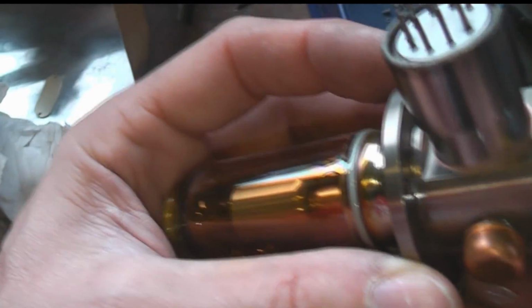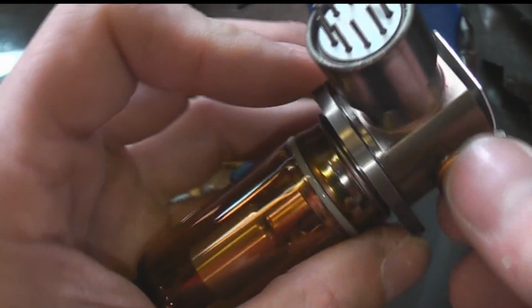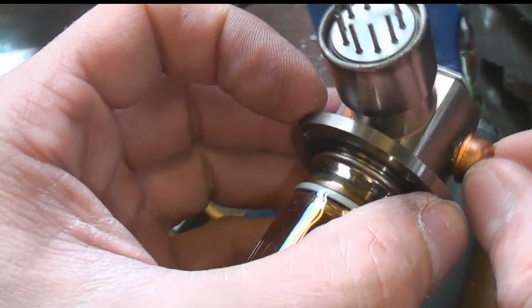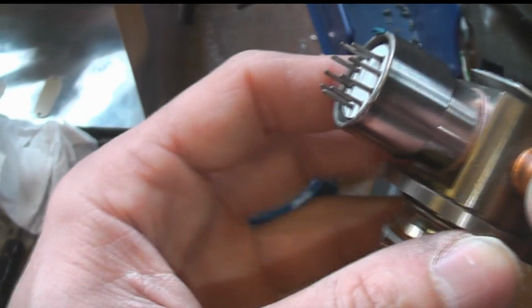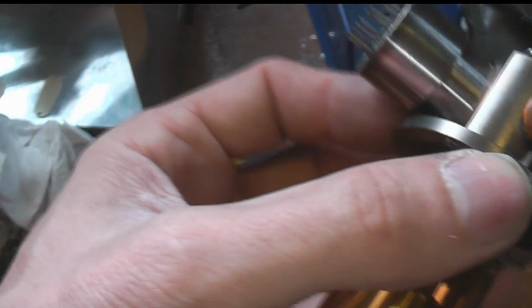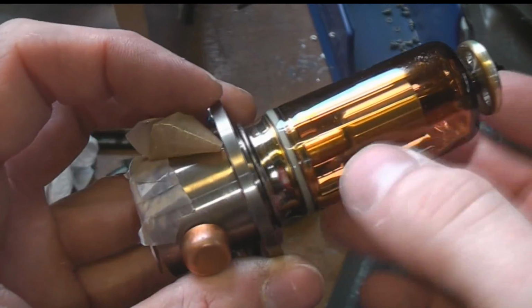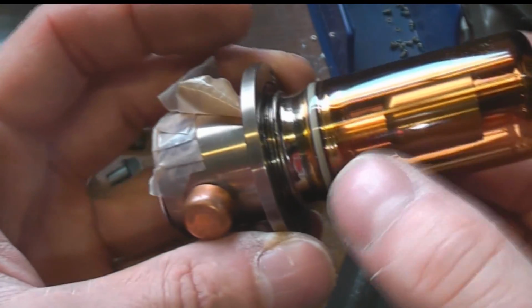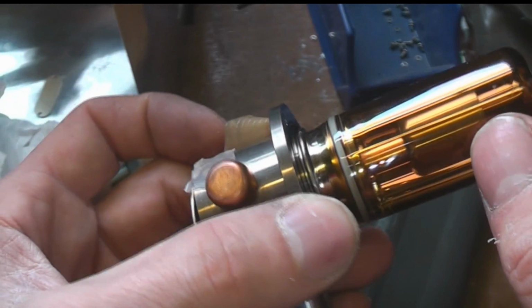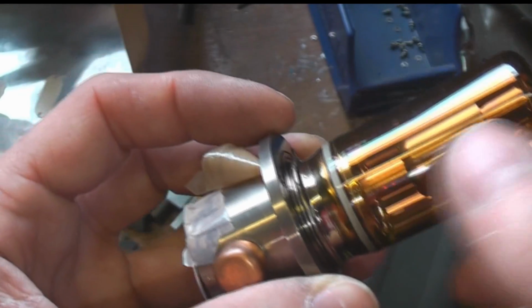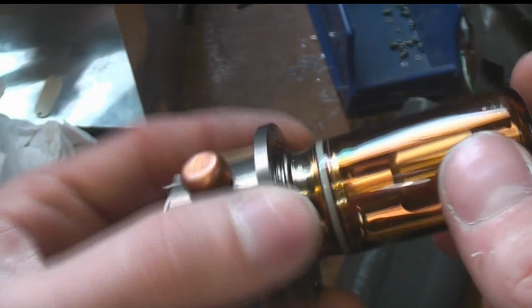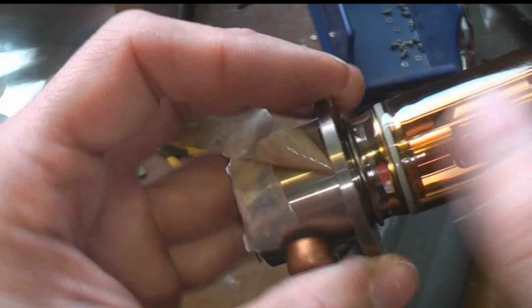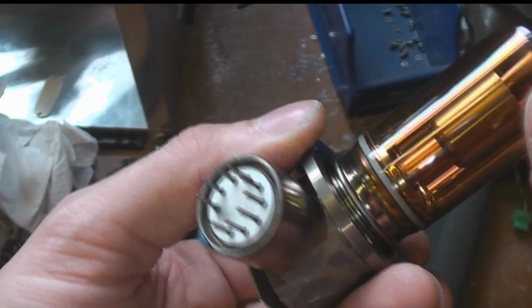So this whole assembly is all welded together, and that'll be the vacuum seal. I'm guessing that copper might actually be a cover over the actual seal, or it could be glued or brazed over to provide, obviously this thing will be at a high vacuum. And this is the characteristic slightly brownish glass that you tend to see in X-ray tubes, which I believe is to make it very, very slightly conductive, so that you don't get charge build up on the glass surface, which can mess things up. So it's just to provide a very, very high impedance drain away to avoid that.